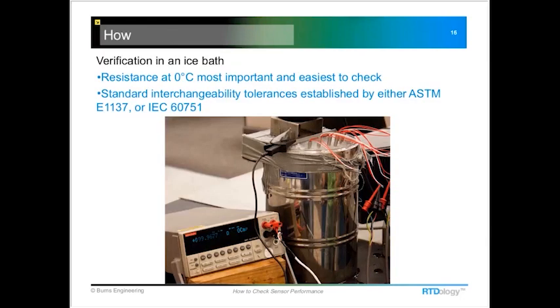After we get a good insulation resistance reading, the next test I like to do is in an ice bath. An ice bath that's put together correctly can give you really good accuracy, in the range of plus or minus 0.002 degrees C. They're quite easy to make up and very accurate, and it's also the point that the manufacturers test when they build the sensors, so you'll be able to verify the original specs for the sensor by doing this ice bath check.